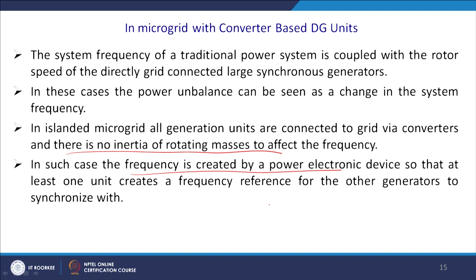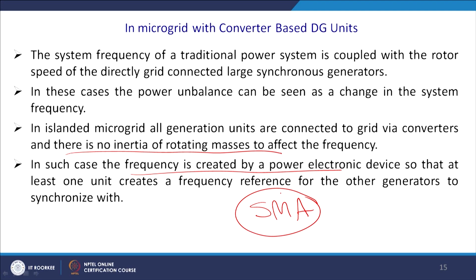In an islanded microgrid, all generation units are connected to the grid via converters, and there is no inertia or rotating mass to affect the frequency. So, it is a low inertia system or zero inertia system. In such a case, the frequency is created by the power electronics devices, so that at least one unit, something like a pilot inverter, creates the frequency reference for the other generators to synchronize with. You can refer to SMA, a company that has an off-grid inverter, Sunny Boy. These synthesize their own microgrid, and all the solar inverters are required to be synchronized with that. It is the off-grid solution from companies like SMA.